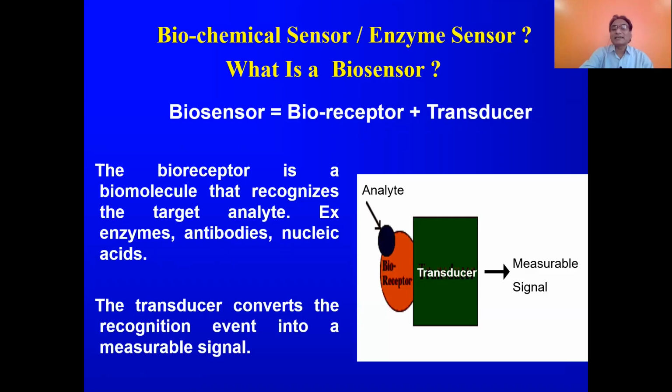The blood glucose that we measure, nowadays there are sensing strips, you must have seen them. On that strip there will be some enzyme. For glucose, glucose oxidase is the enzyme. So that glucose oxidase is going to be the bioreceptor, and that is highly selective. Glucose oxidase will react only with glucose, not with any other. Like in blood there will be cholesterol, urea, urease, sorry. So that glucose oxidase is not going to react with cholesterol or any parameter other than glucose, and therefore biosensors are by default highly selective.